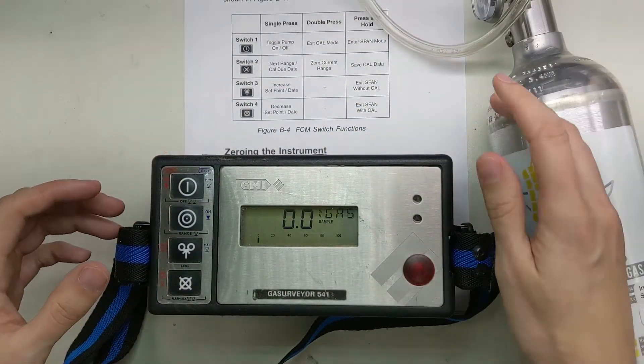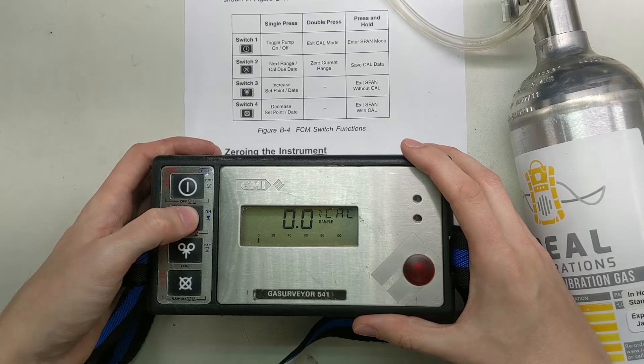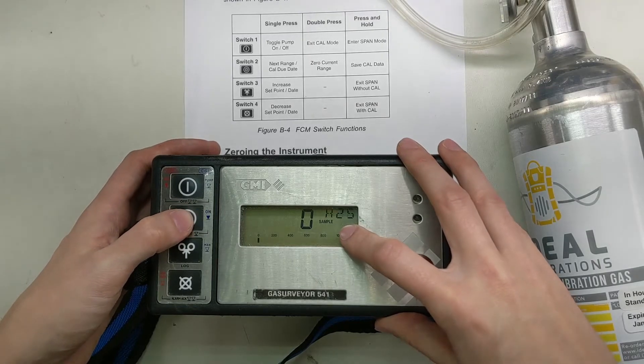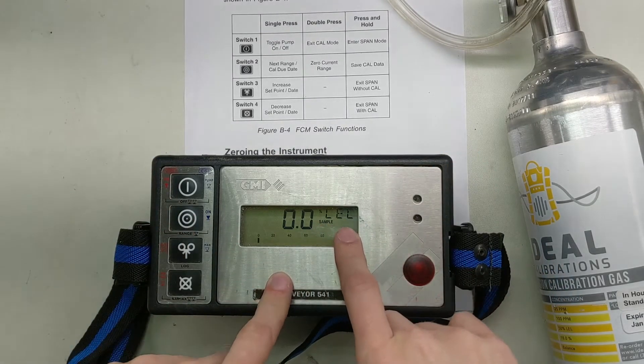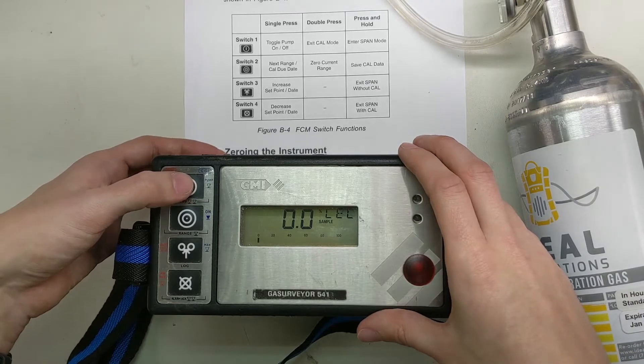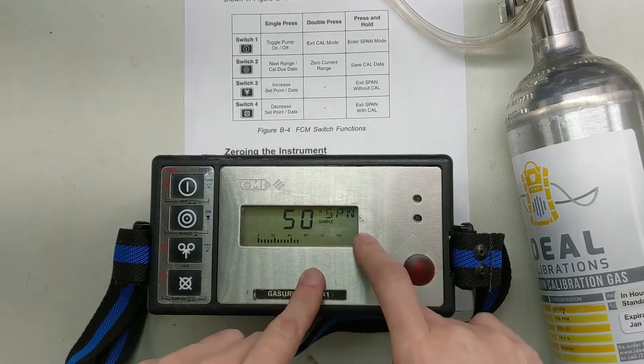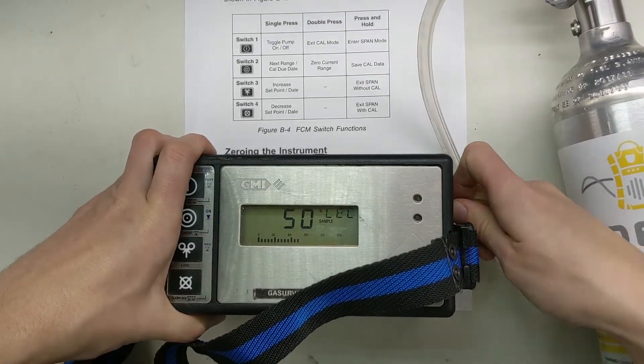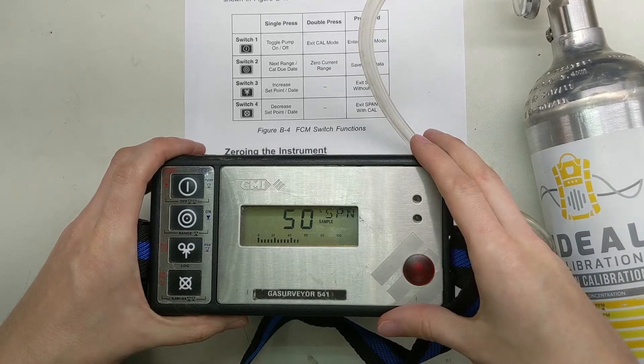Now this is going to be all ready. So now let's put this unit into the actual span mode. Right now we're looking at percent gas. In order to get ourselves into span mode, we're going to press and hold this power button here. Now you see the monitor goes to 50% and LEL span. This is what gas it's looking for right now. I'm going to put this on here. It's our 50% LEL gas.